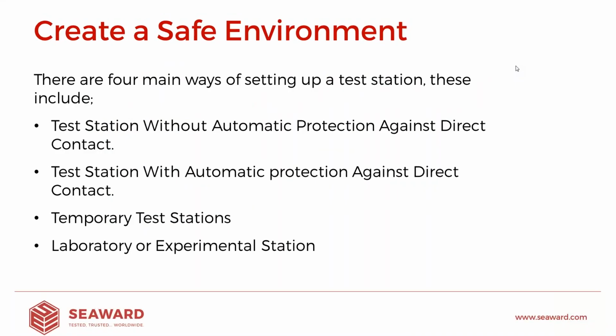So now we've created all the individual elements that ultimately sum up a safe working environment. Let's have a look at some of the ways you can create a test station. Traditionally, there are four main ways of setting up a test station. So there's a test station without automatic protection against direct contact. What that means is effectively the operator can touch the product under test. We have test stations with automatic protection against direct contact. Therefore, there's a barrier between the operator performing the test and the actual product under test. We can also talk about temporary test stations and laboratory or experimental stations.